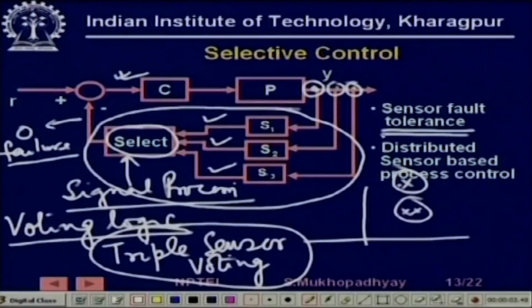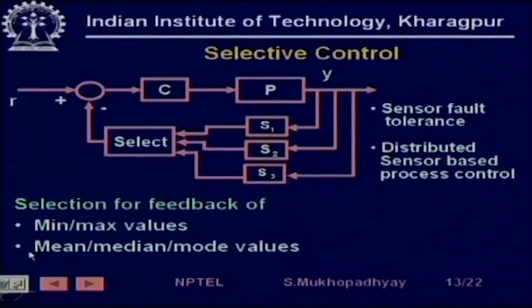By doing this you can achieve a certain degree of sensor fault tolerance. You can use sensor selective control, and there are even other situations where you can do median filtering — selecting the middle value when one sensor gets a large noise spike — so you can reject noise better. Selection of feedback using minimum, maximum, mean, median, or mode values, depending on the application, is selective control. It is a common sense approach but can sometimes give significant protection from sensor failures.